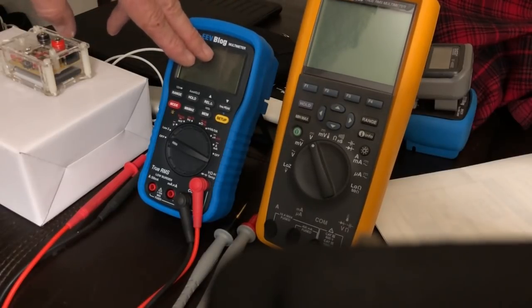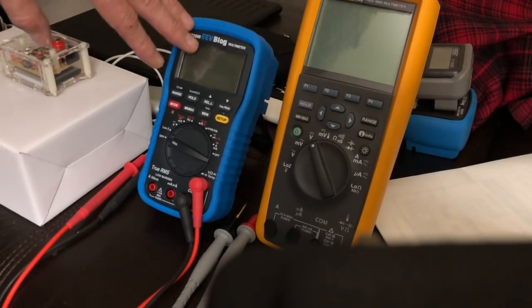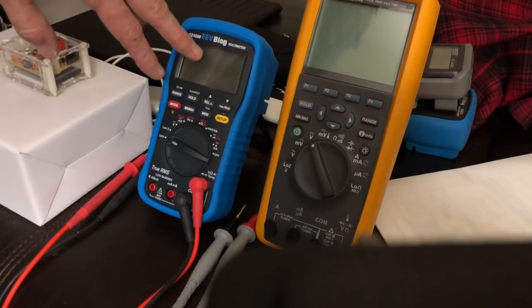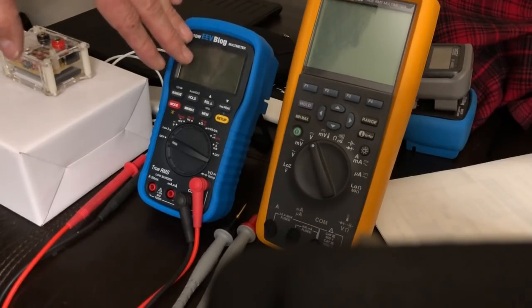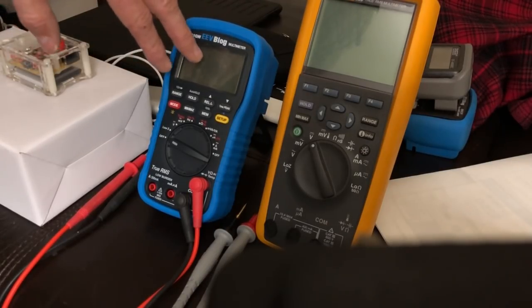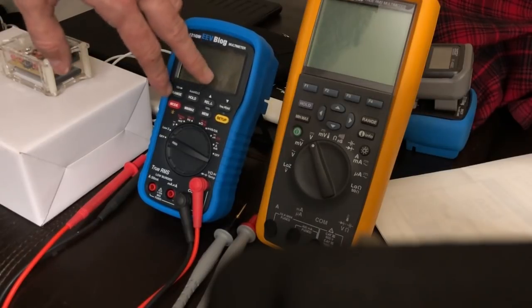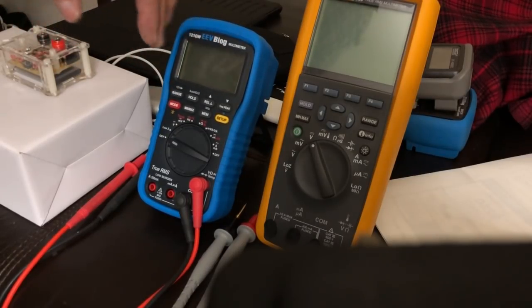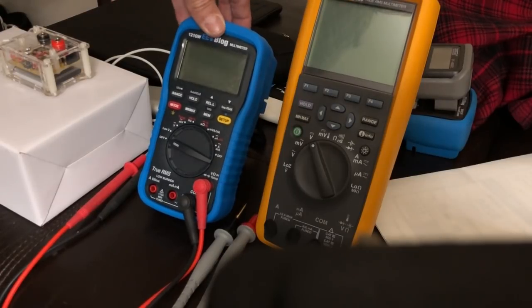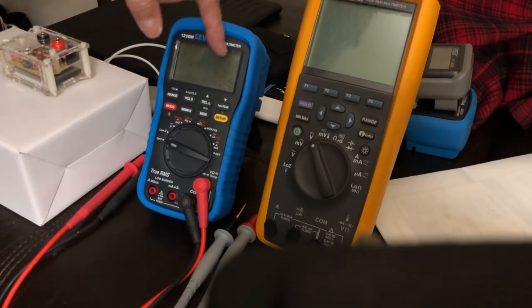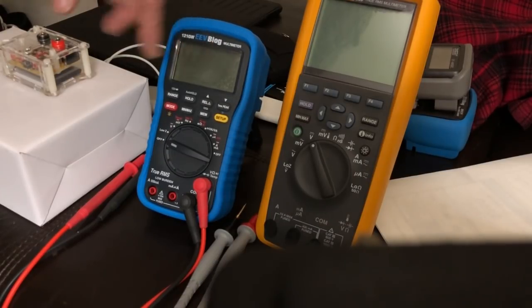This requires at least 40 millivolts, I may be wrong on this number. I didn't go exactly from 35, I was doing it in 5 millivolt increments. So I went to 35, it didn't change. I went to 40, it changed. I did that three times, and both times it changed. So somewhere between 35 and 40 millivolts is required before it actually re-registers.